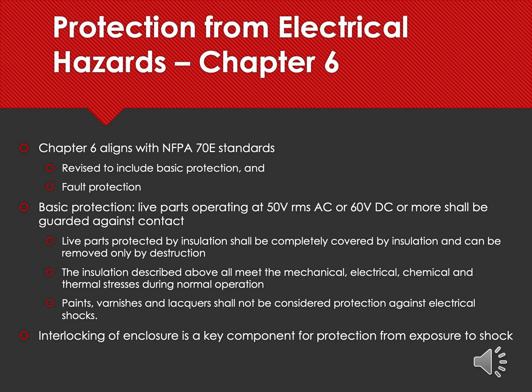So basically, basic protection calls out any live parts operating at 50 volts AC or 60 volts DC shall be guarded against direct contact. So meaning a protection against direct contact, which is primarily shock hazard. And secondly, from indirect contact perspective, there is a fault protection like arc flash hazard, one must be protected as well. So new definitions have been added to these sections, and 6.2 and 6.4 provide some additional information within the standards for what those details are. So each machine has unique requirements, and hence it has to meet the fundamental premise of protecting the people from hazards. Though 79 is considered an electrical safety document, it aligns with 70E and 70B standards for electrical safety and recommended practice for electrical equipment maintenance. So lack of proper maintenance and lack of use or misuse of PPE can often result in a hazard.